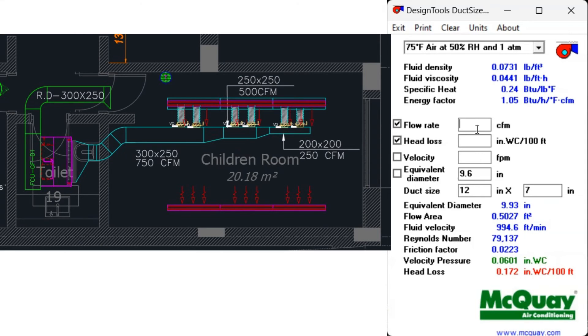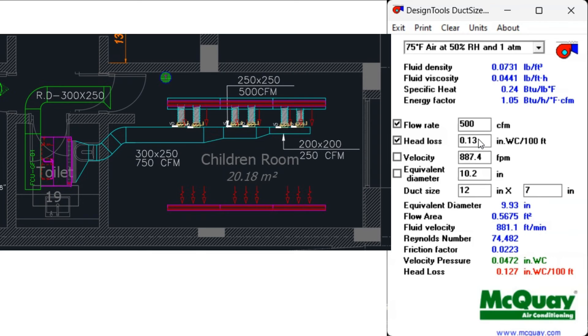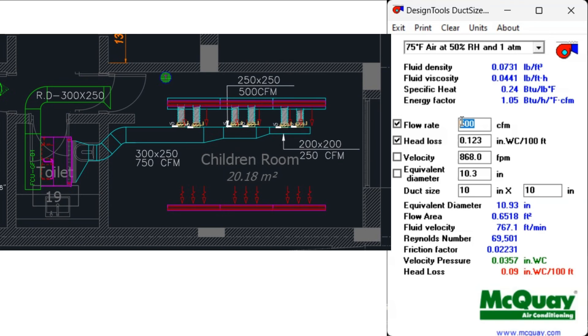I use this friction value of 0.123 as the equal friction for the entire duct design. For the next airflow rate of 500 CFM, I input the friction rate of 0.123 obtained from the initial flow rate at 1000 FPM velocity — the duct size becomes 10 inch by 10 inch. I followed the same method for the next flow rate of 250 CFM and got an 8 by 8 duct size.